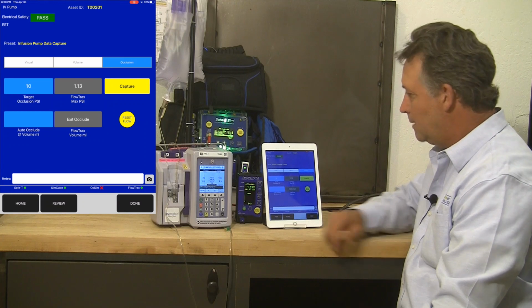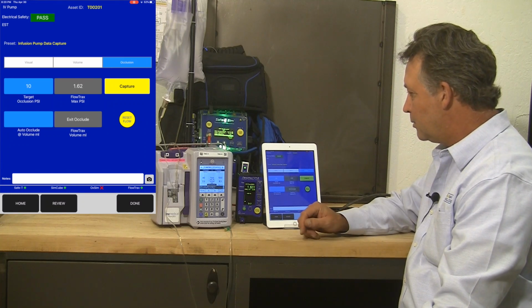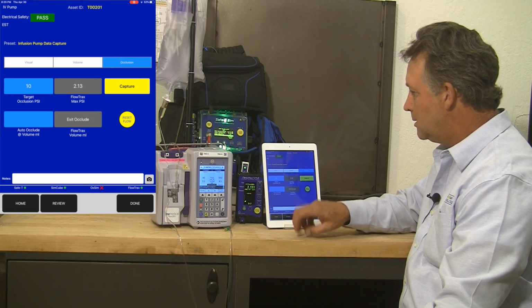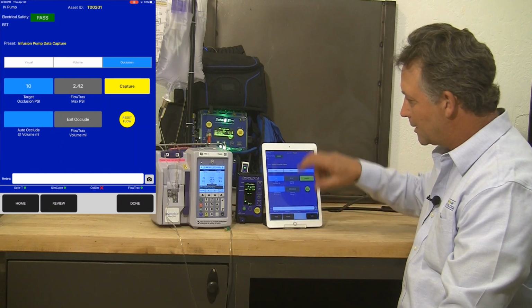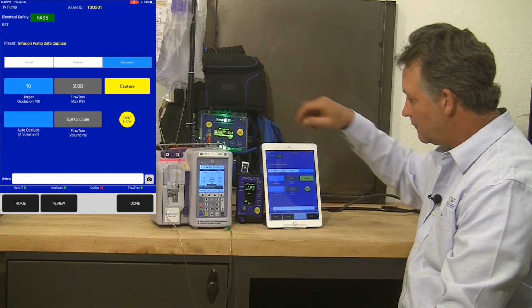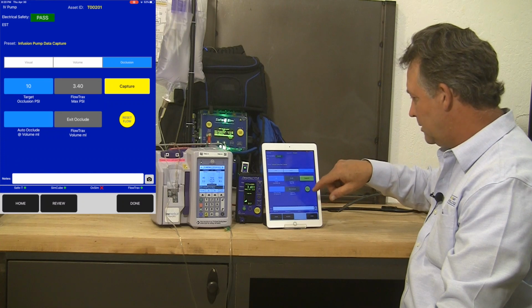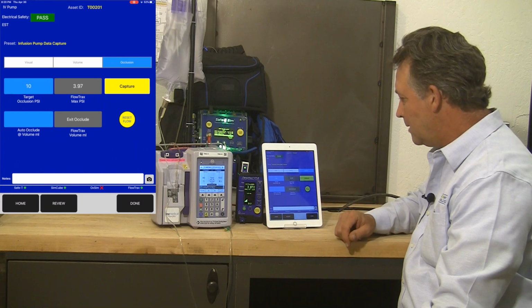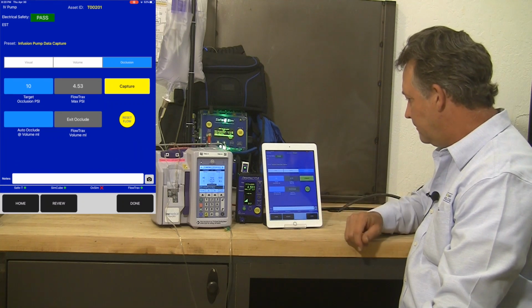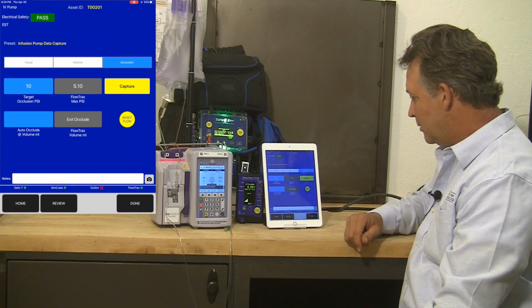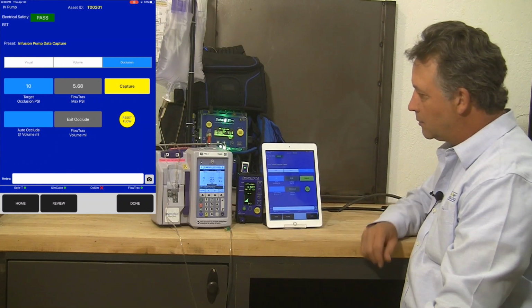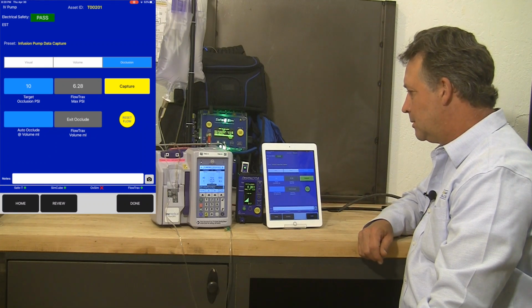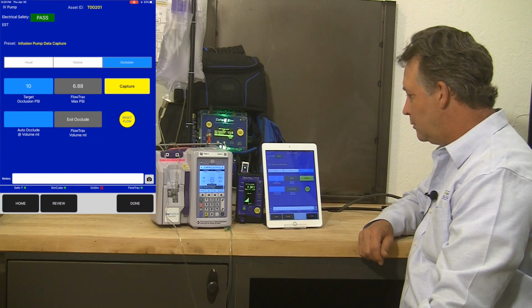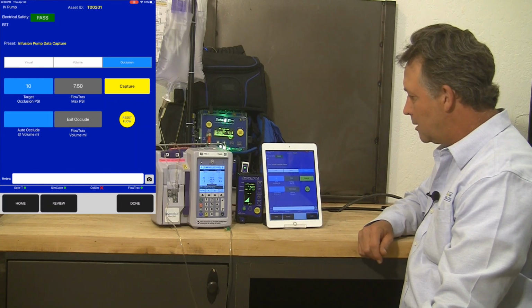So again, the IV pump is continuing to try to push fluid. The IV set is occluded because we're electronically, wirelessly controlling the FlowTrax for that occlusion. And we can see the pressure is climbing. We're at 4 psi. And as soon as it reaches close to 10 psi, the pump will detect that occlusion alarm, stop pushing fluid, and we'll be able to capture our peak or max pressure into an electronic record.